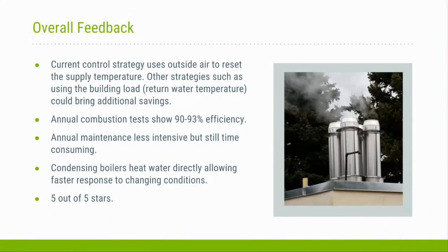So for today, I was informed that we had an 11-degree split from our supply to our return. So we're still doing a lot better. And in our annual combustion test that we do out here, we're showing these new boilers at 90 to 93%, which is pretty good for the altitude that we have here.